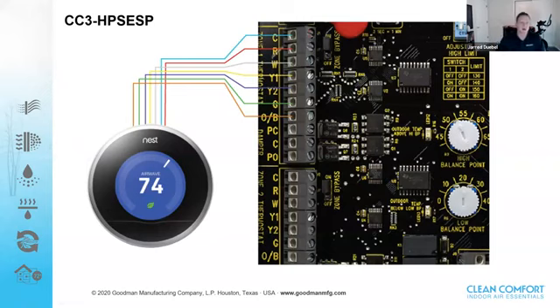Here's just a little bit more of a close-up on the panel. Again, you've got your hot and common, W, Y1, Y2, G, and then O/B for the reversing valve. And then of course, Y2 is going to convert over to W2 when we switch into heating mode.